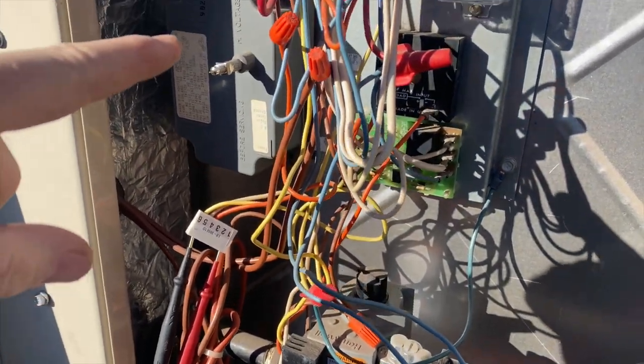Another thing too, this is a screw-on type igniter so we want to make sure that it's tight. But this tells us that our centrifugal switch is closing. To verify that, to show you how this works, I'm going to remove my jumpers and then just power it back up so it's not calling for heat, just to show you that there will be no voltage unless there's a call or basically unless that guy's spinning. So we have no call for heat, as you can see my meter never shows zero but this is like millivolts, so you can see that there's no voltage.